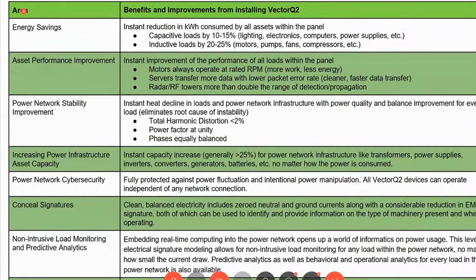So the three areas that we focus on are harmonics, power factor, and phase balancing. One of the most important parts, and that's traditional power quality, is harmonics and power factor, right? Voltage. But phase balancing, equal balances across phases, results in direct loss. If you have an imbalance in phases, you have neutral current in the network downstream, and you have eddy currents in the transformer upstream. And so power quality needs to include all three: harmonic, power factor, and phase balancing, all in real time. If all three of those are addressed in real time at once, then you have stability in the network. That is the root cause of instability. And then, quickly, some of the other benefits are increasing the power infrastructure asset capacity, like transformers. When there's an imbalance in transformers, the capacity of that transformer is limited to the highest used phase.